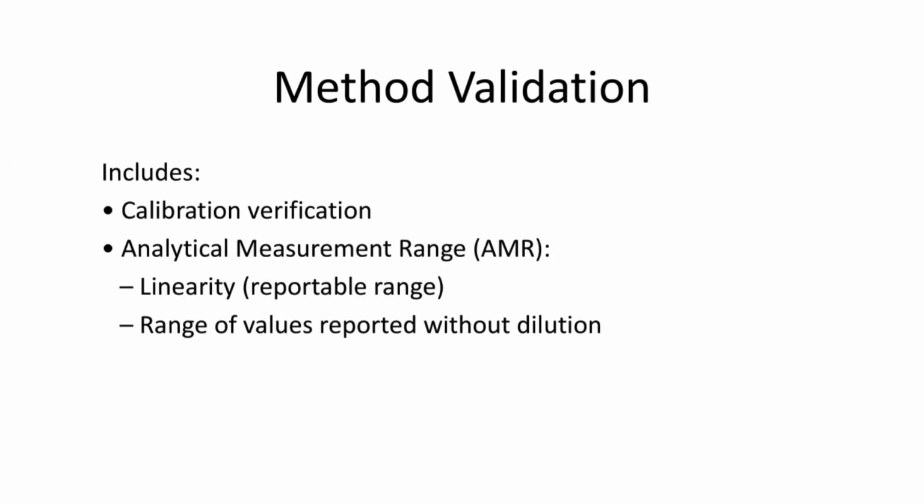Then there is method validation. This includes calibration verification, which confirms that instruments are properly calibrated. It also involves the analytical measurement range, sometimes called the AMR. This includes linearity, which is the reportable range, and the range of values for a procedure that may be reported without dilution.